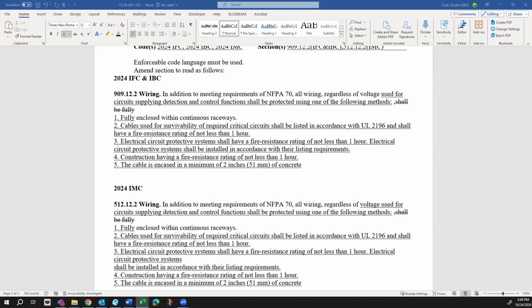But this is like the actual wiring for the ventilation system, that's still required to be 2 hours. No, I agree. Yes. The whole part of that falls under a different section, but this is detection parts that are not associated with it. Yeah, I'm talking about the fire alarm wiring for detection, which is the ones serving the initiating devices.